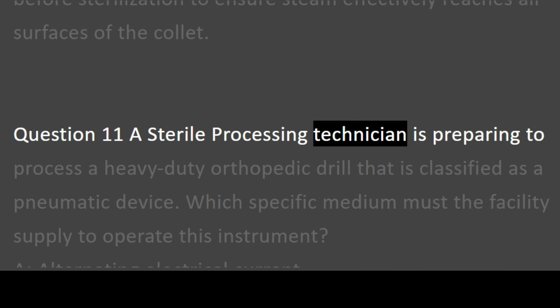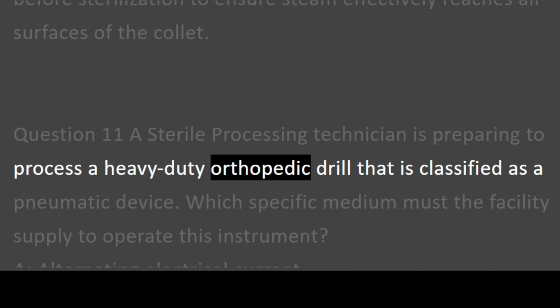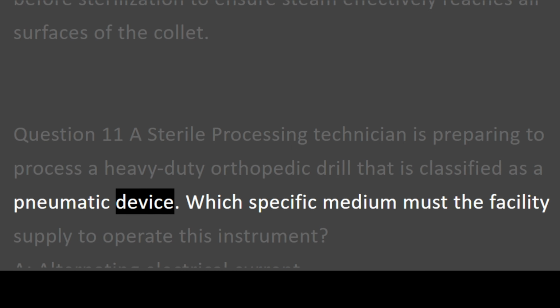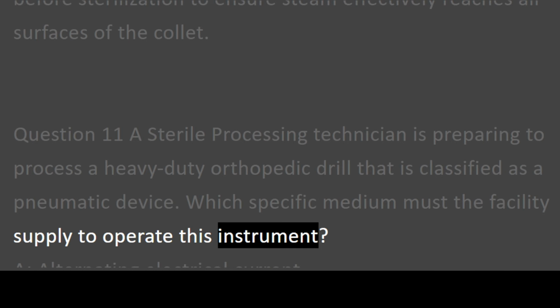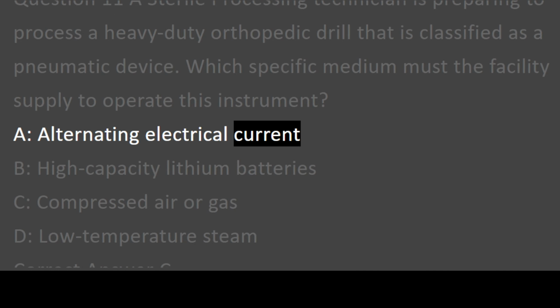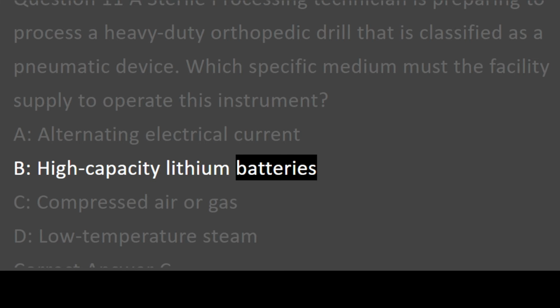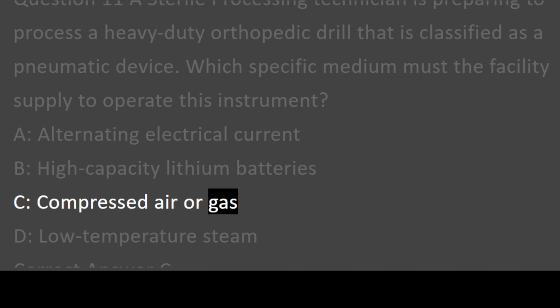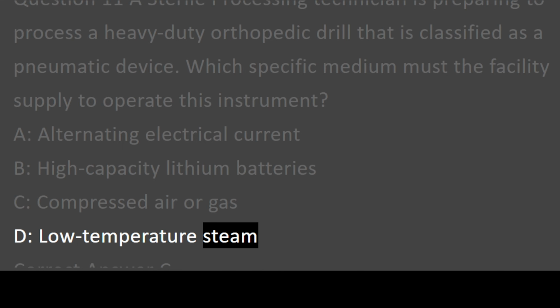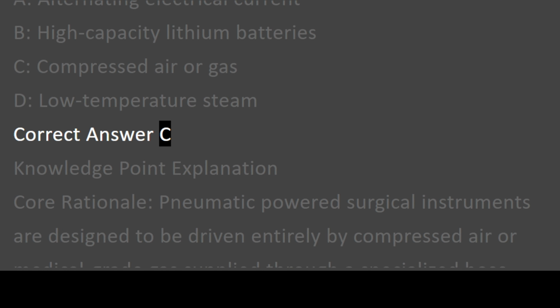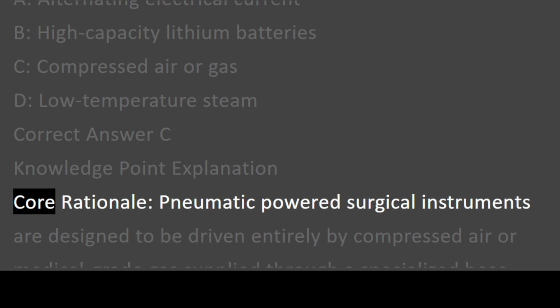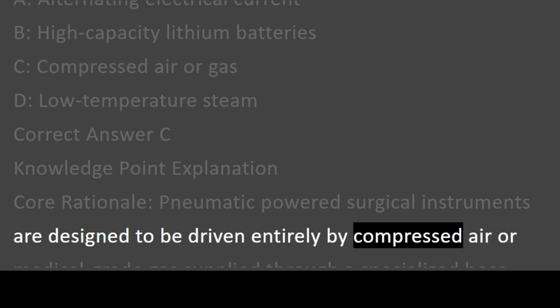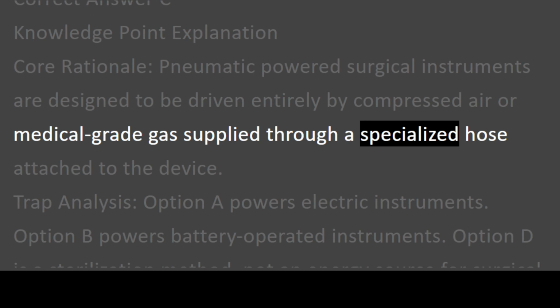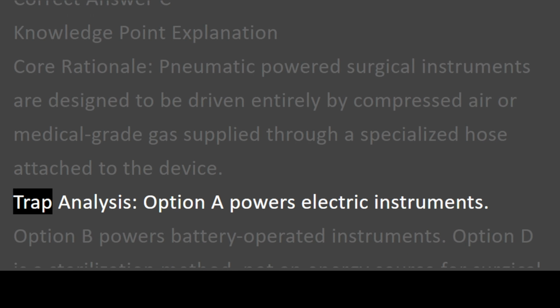A sterile processing technician is preparing to process a heavy-duty orthopedic drill that is classified as a pneumatic device. Which specific medium must the facility supply to operate this instrument? A. Alternating electrical current. B. High-capacity lithium batteries. C. Compressed air or gas. D. Low-temperature steam. Correct answer C. Knowledge point explanation. Core rationale. Pneumatic-powered surgical instruments are designed to be driven entirely by compressed air or medical-grade gas supplied through a specialized hose attached to the device. Trap analysis.